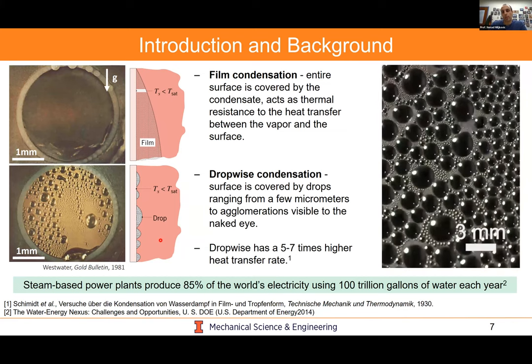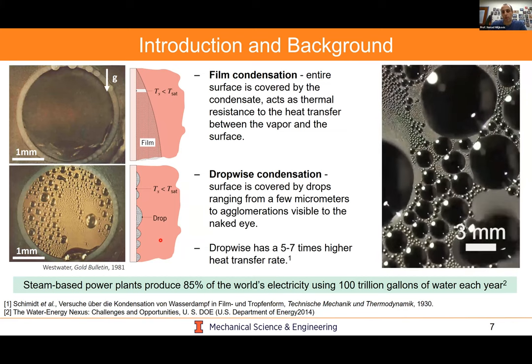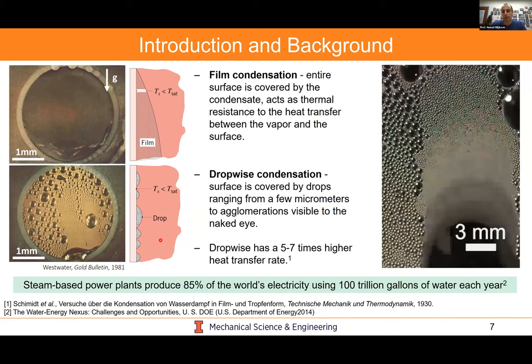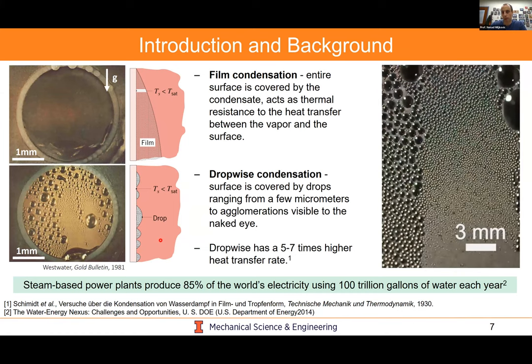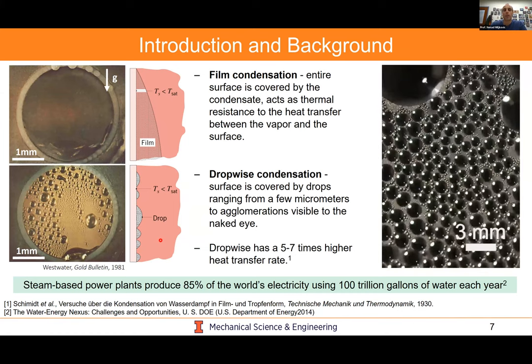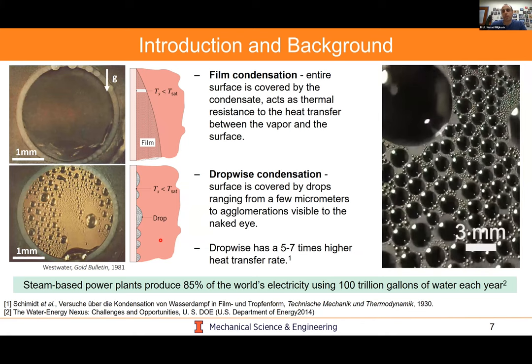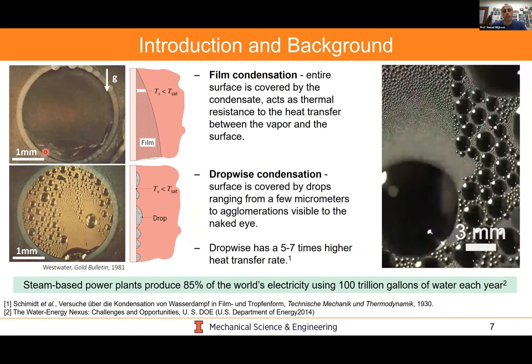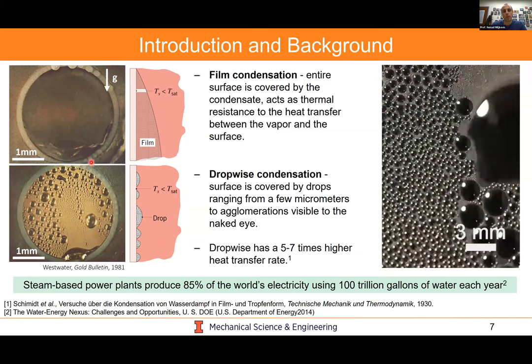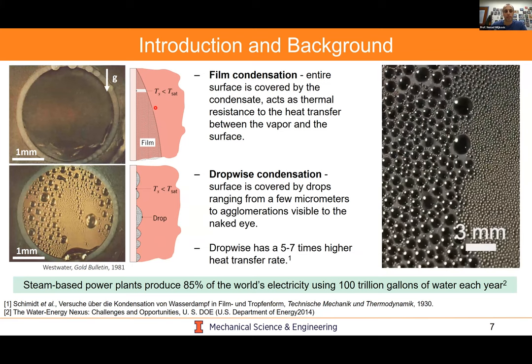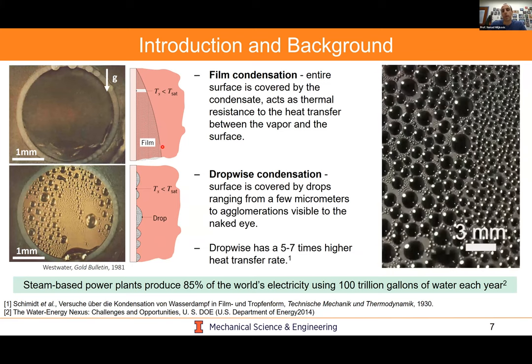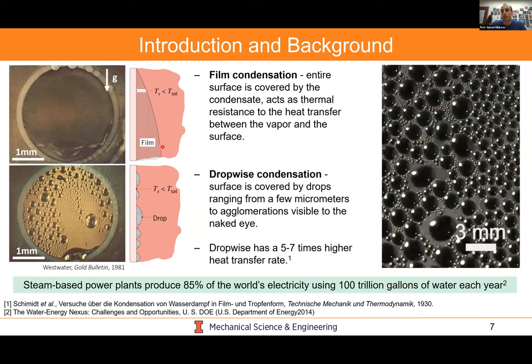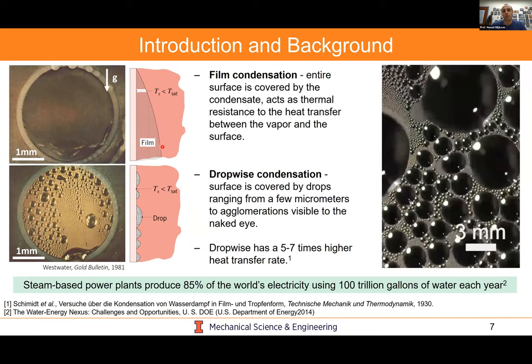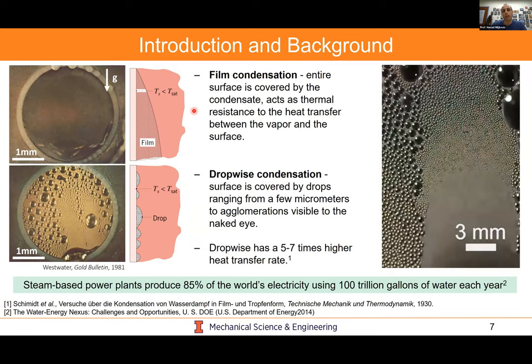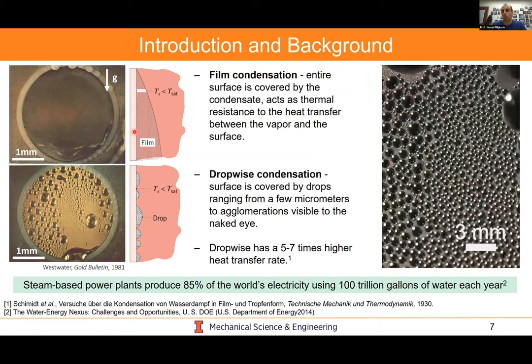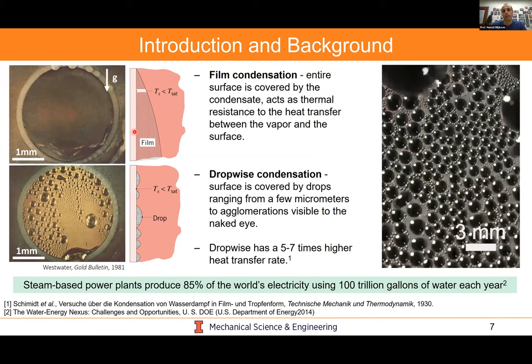Typically, this condenser is just a bare metallic tube—copper, nickel, steel, or stainless steel, depending on where you are in the world. But this condensation process tends to form a very thin liquid film, as you see in the top left image. This liquid film inundates the surface and causes a barrier to heat transfer, reducing efficiency from the steam side to the coolant side, where typically multiple tubes have coolant water flowing on the inside.